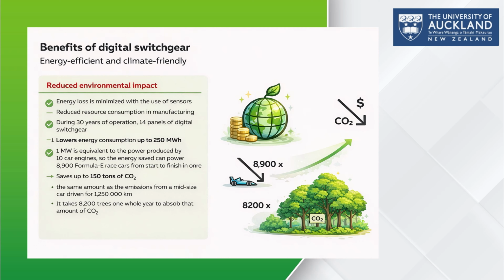The digital switchgear significantly reduces energy losses by using advanced sensors. It also cuts down on the resources needed during manufacturing, which reduces overall environmental impact. So if we look at a typical installation of 14 digital switchgear panels over a 30-year operating period, the benefits become very clear. We can reduce energy consumption by up to 250 megawatt hours. In terms of emissions, this translates to a saving of up to 150 tons of CO2. That is equivalent to the emissions from driving a mid-sized car for 1.25 million kilometers. And to absorb that much CO2, naturally we would need 8,200 trees working for an entire year.